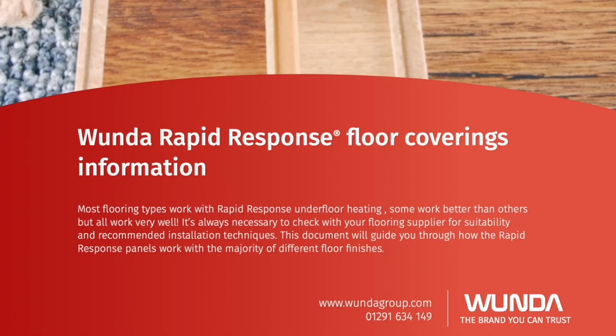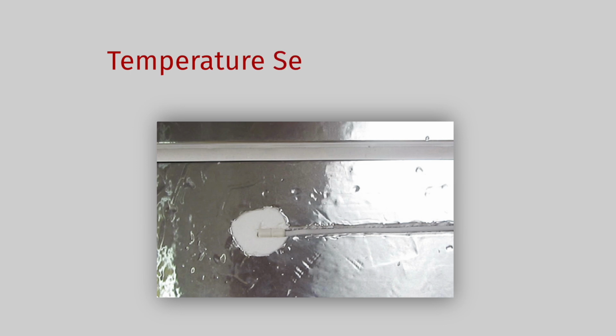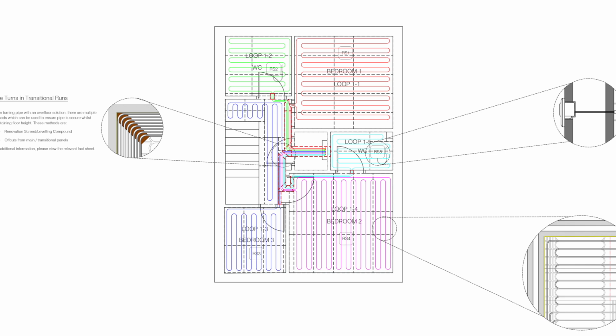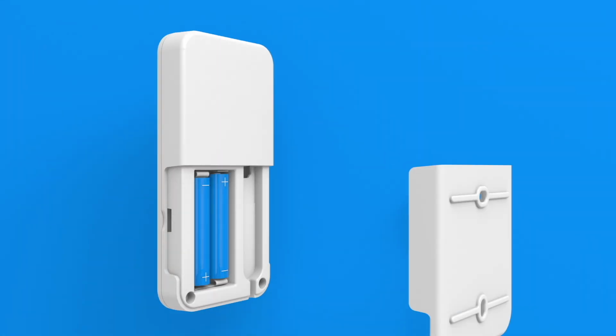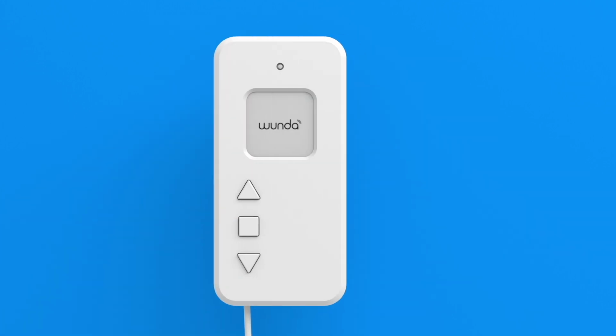Follow the advice and instructions in the floor coverings information document. The only additional requirement is the installation of a temperature-sensing floor probe. To ensure a probe is included in your bespoke Wunda Rapid Response system design, simply inform your sales advisor about your choice of floor covering when placing your order. This crucial component ensures your underfloor heating is limited to the maximum temperature recommended by your flooring manufacturer.